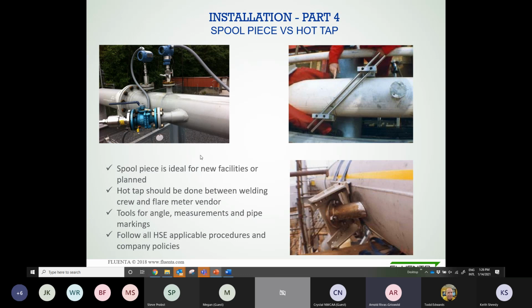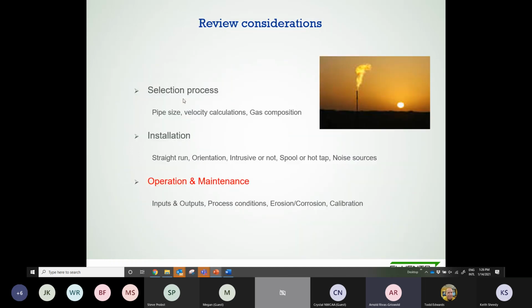I would say probably 95+% of the applications we do are with spool pieces, because they want to make sure that the angles are correctly calculated and the welding is more precise. And at the same time, you may want to reduce the uncertainty related to the installation by doing that. So there are two options depending on the facility, but of course we recommend the spool piece version for it.